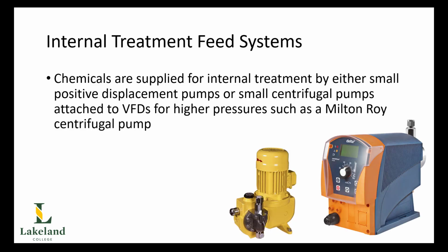Okay, so what's pumping this chemical is simply a pump, and these pumps are typically either plunger pumps, which is a type of reciprocating pump, or we also sometimes see centrifugal pumps, such as the one pictured here bottom left, which is a Milton-Roy centrifugal pump that's used for high pressure chemical injections.